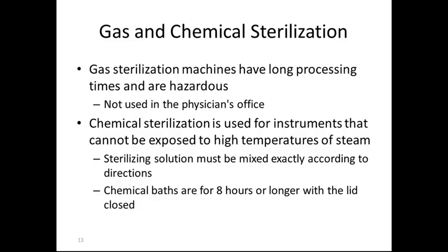Sterilizing solution must be mixed exactly according to directions. Chemical baths are for up to 8 hours or longer and the lid is closed. After instruments have been immersed in chemical sterilizing agents, they should be rinsed with sterile water.